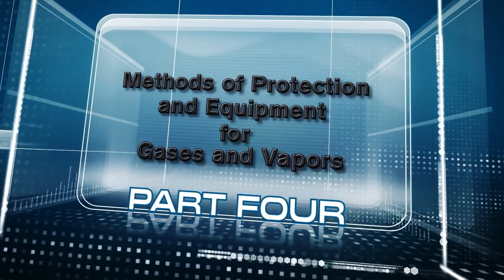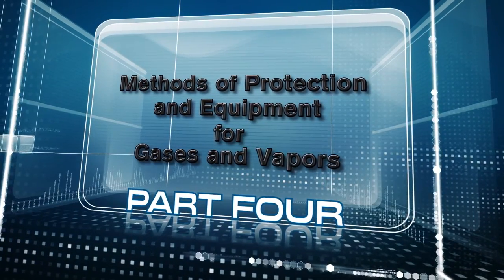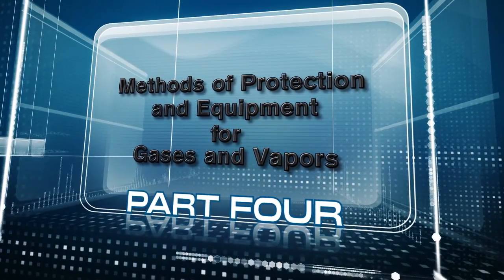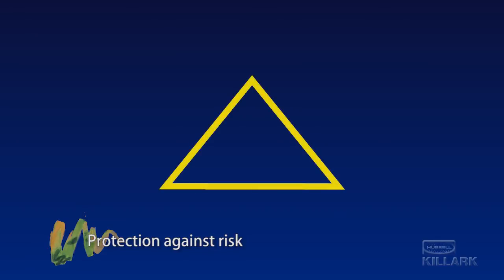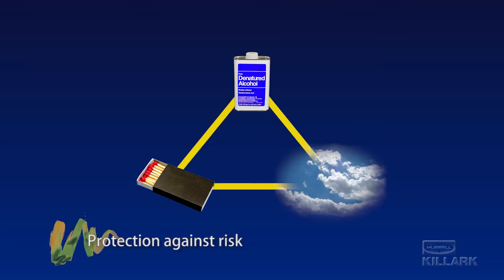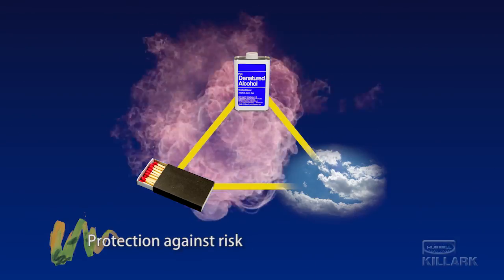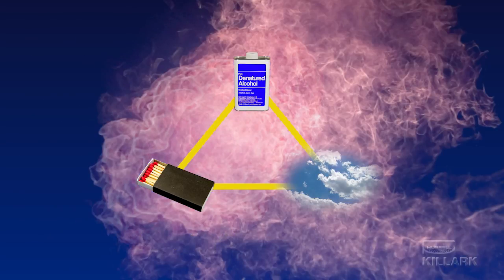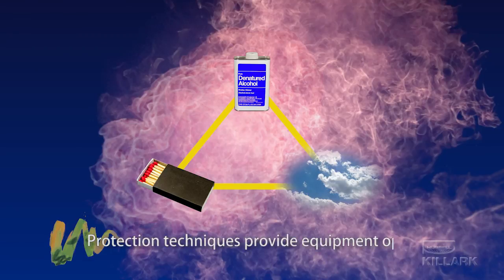Part 4. Methods of protection and equipment for gases and vapors. Recalling that the fire triangle brings together the three essential components for combustion to occur: fuel, oxygen in the air, and a source of ignition, it is now possible to begin addressing the explosion potential identified during the risk analysis. A variety of approaches are available for the design of these specialized electrical installations. These are made possible by the alternative protection techniques that provide equipment options for the specific hazardous locations.